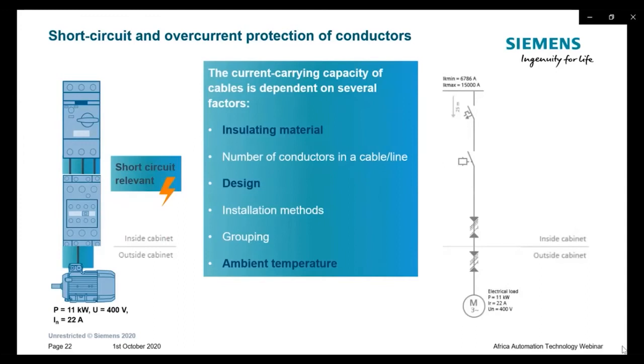It's the number of conductors or cables in a line. It's the design itself, but also the installation method, as installation method inside of the cabinet or outside of the cabinet can be completely different. Grouping, how the arrangement of the different load feeders and conductors is done in the application. But also the ambient temperature takes an important role in dimensioning and designing the right protection devices, switching devices, and conductor material.